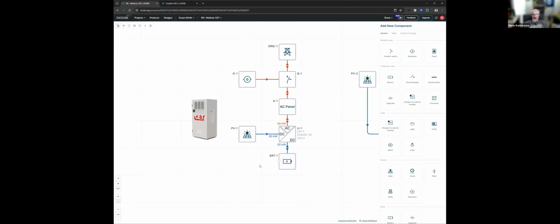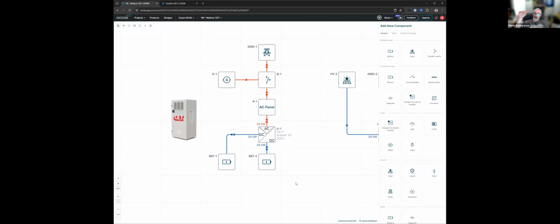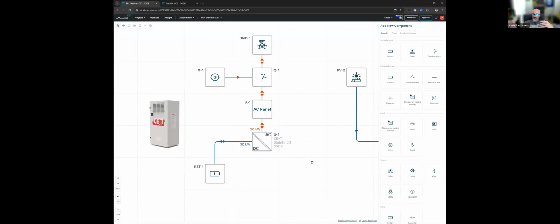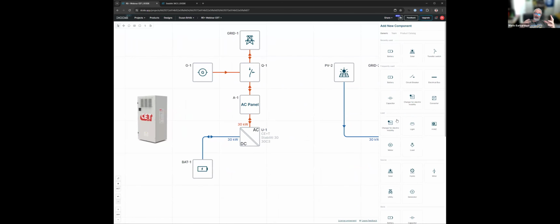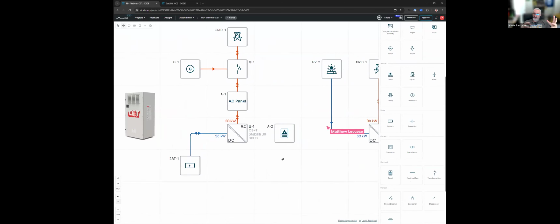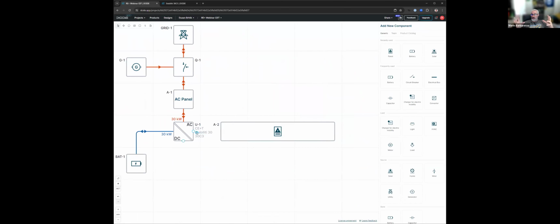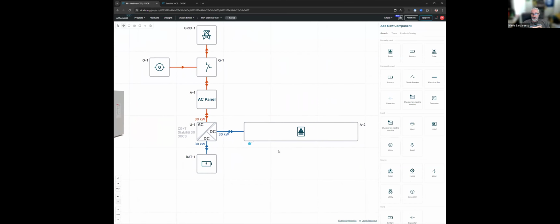Thanks for saying that, because those DC ports are flexible enough to add a second set of battery, or you would have one DC port to charge your battery and the other DC port to have a DC bus, where the behavior of the DC would be more to maintain a certain voltage instead of charging a battery. That DC port would create a DC coupled network in a facility where LED lighting could be added on, or any DC load could be added on. So that's the difference between using the DC port as a battery charger or using your DC port as a rectifier with constant voltage. And that's what can be done with the stability.